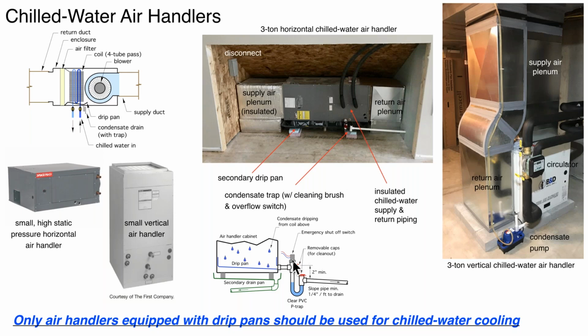Some of them also come with a switch, and that switch is going to be tied into the low voltage control system for that air handler. The purpose of the switch is, if the water level in the trap rises, let's say we have a blockage either in the trap or in the piping taking that condensate away, that switch can actually open and it can prevent the air handler from operating. The idea is we don't want the air handler operating, producing more condensate, only to have that condensate overflow the trap or otherwise leak out of the unit.